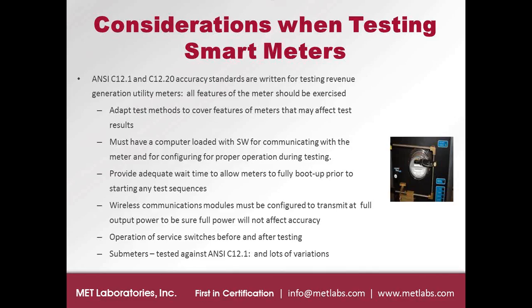Again, any communication modules, AMI modules, AMR, they've got to transmit at full power to make sure that the accuracy is not going to be affected by that higher power. If we see problems, at times we may test with and without exercising those communication modules. Service switches may be embedded in the meter, we see those very often these days, and we want to make sure that we can actuate those, again, usually using the software provided for communicating with the meter. So you're making sure that there are no problems there.